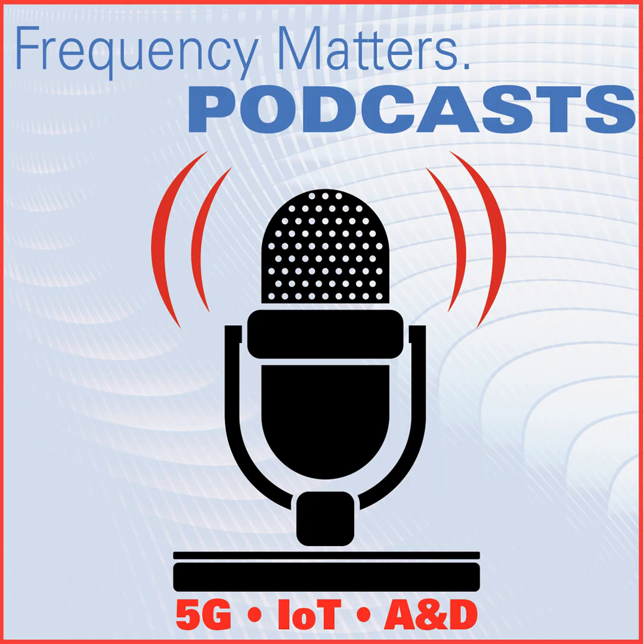As we go through our marketing, the premise we thought is that if we could give somebody a big enough power amplifier or transistor, they could radically reduce the system size. In this case, we've given them a high enough power level transistor that we can allow them to drive the linear accelerator with solid state. There are a lot of benefits in terms of pulse shaping and the ability to do different waveforms that you can't really do with a tube. So that's been one of the exciting ones.